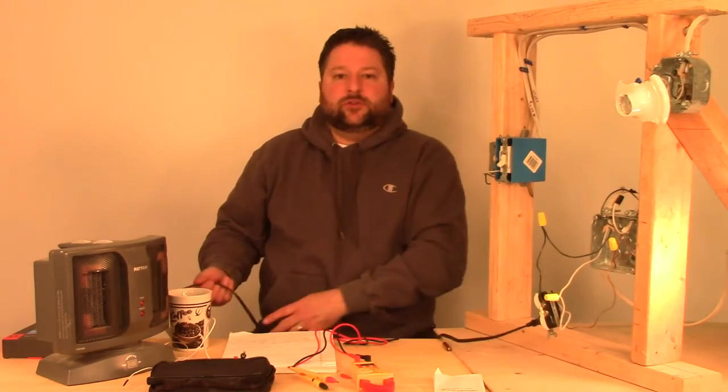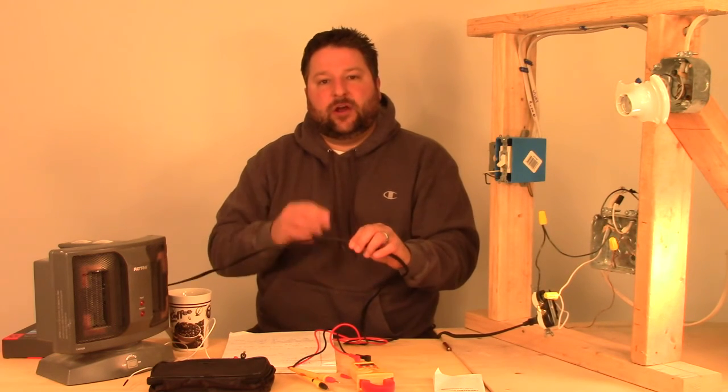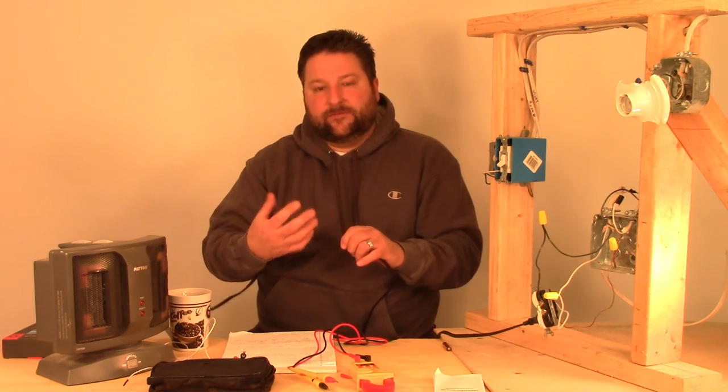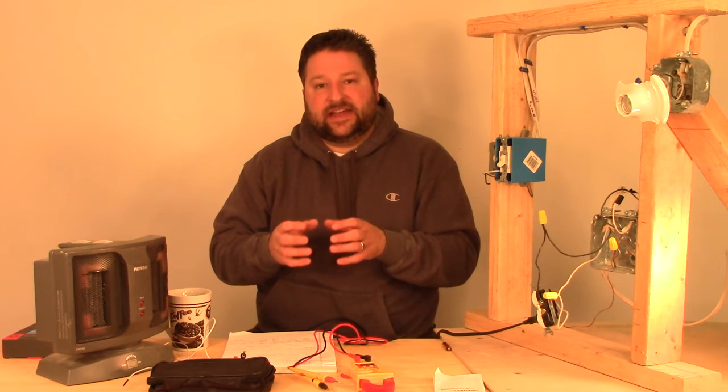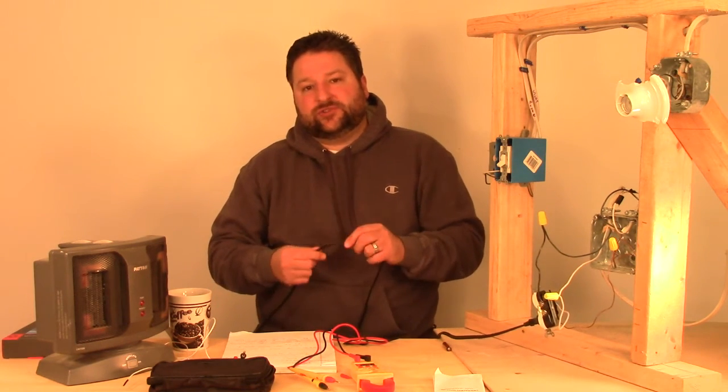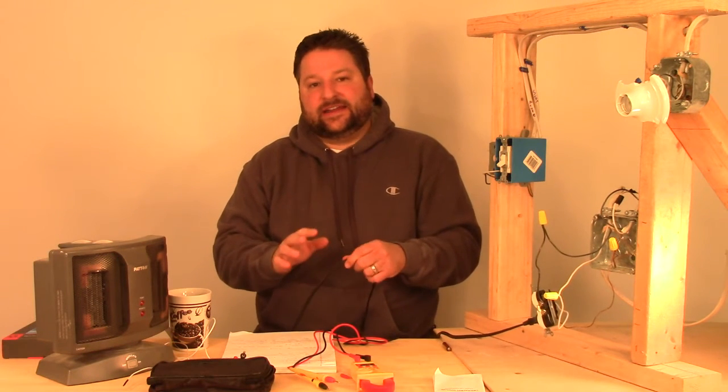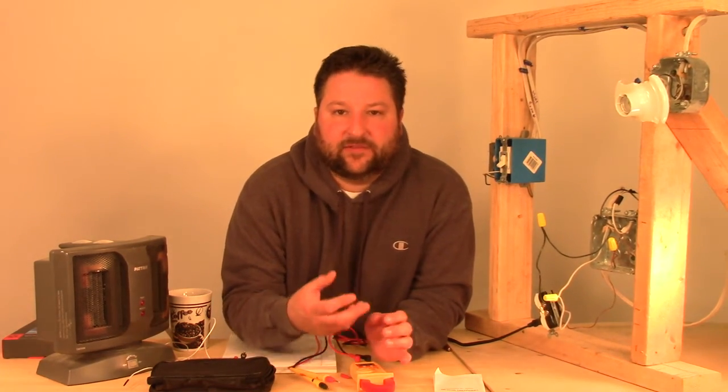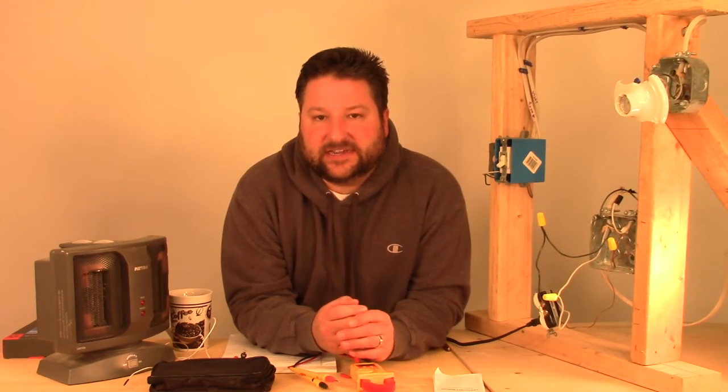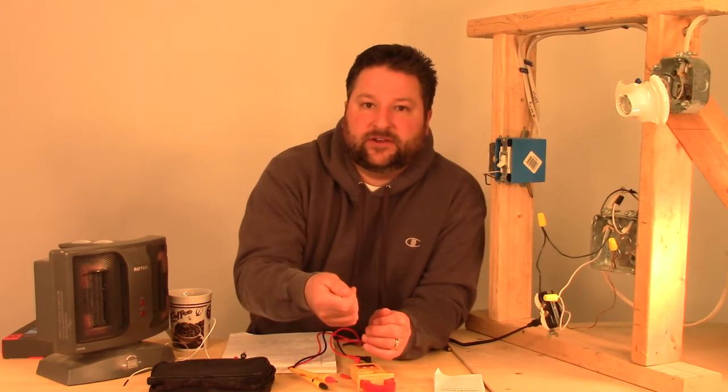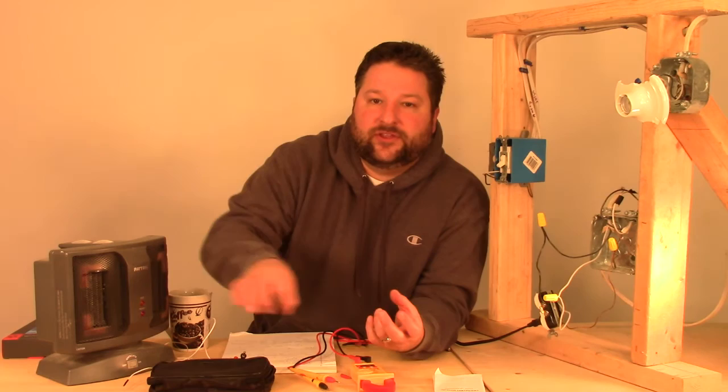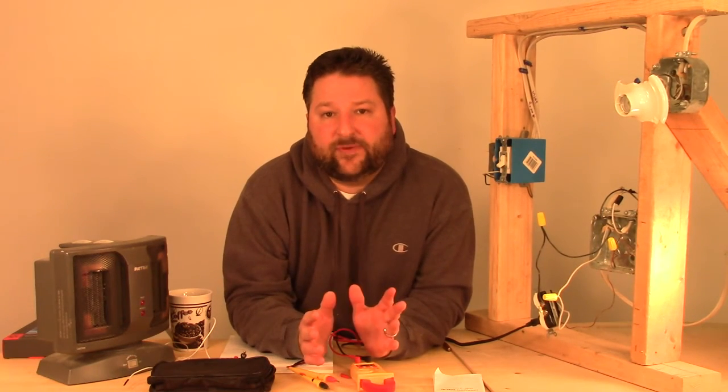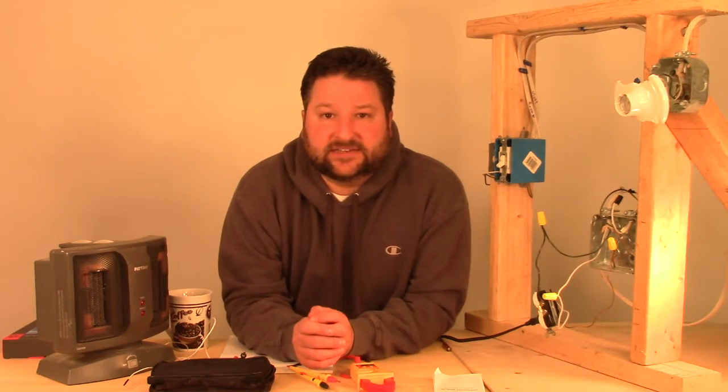Now one thing when you're testing amps, you don't want to go around a wire like the electrical wire coming off of an appliance because it's reading the electromagnetic field around the wire itself. The best one to read is your power or your positive side, the black or red wire. That's the one you really want to try and get your amps load off of. If you clamp across both of these, you're not going to get an accurate reading. So you want to try and get to a point where you can see that power line either in the outlet, pull it out of the wall, and then clamp on the power line coming off an outlet if you're testing it. Or they actually sell things that will plug into the wall that split the power circuit coming out of the wall. Then you plug your appliance into it, and you can clamp around that, and that will actually give you an accurate reading. It's a safe way of doing it because you're not going into the wall or pulling the wire out or messing around inside the electrical panel.